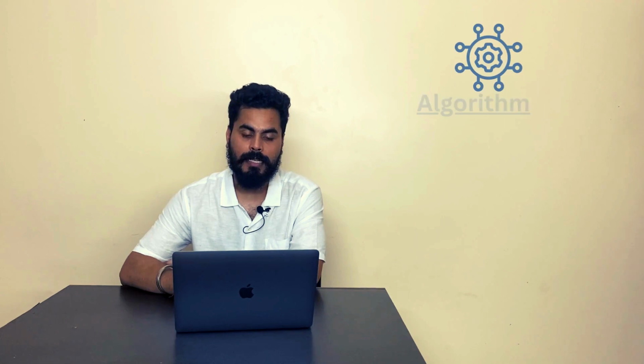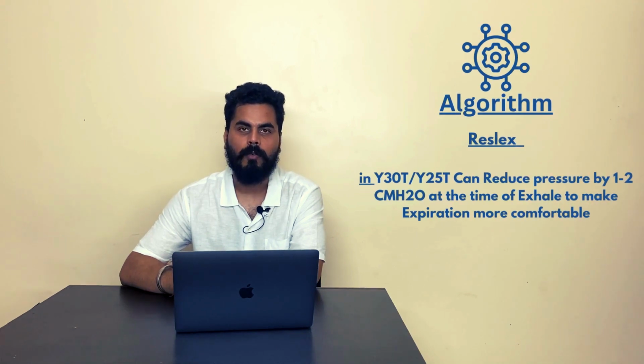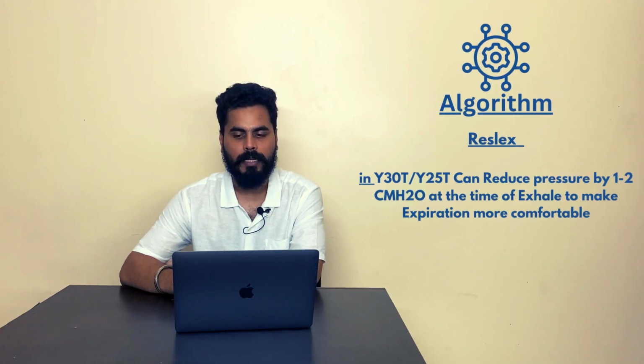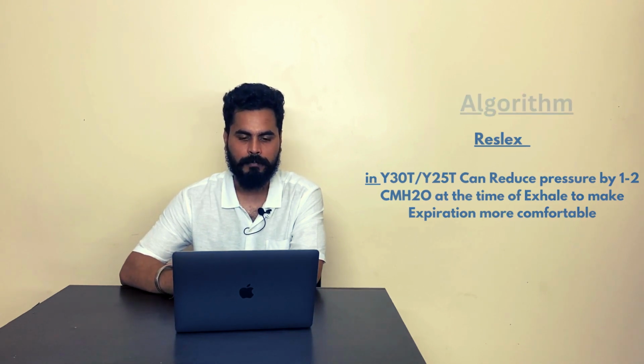Now then there is humidification. This device comes with a humidifier to maintain stable humidification throughout the therapy. There is a Reslex option available as well. This function allows the user to exhale better by reducing pressure by 1 or 2 cm of water at the time of exhale. Detailed reporting is also available through SD card, and there is app-based reporting as well. You can just scan the reporting QR code from the PapLink app and you will get all the details on your phone. For this, you have to contact your device supplier for more details.